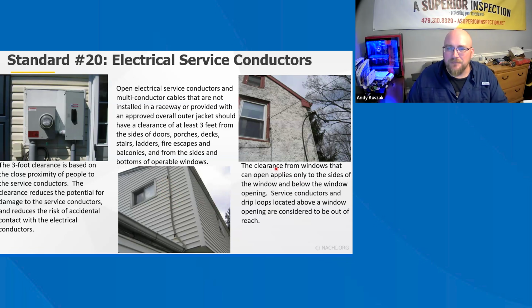Clearance from windows that can open applies only to the sides of the window and below the window opening. Service conductors and drip loops located above a window opening are considered to be out of reach. And I think we're going to go over this in the deck class next week. But a lot of times decks are built after the fact, after the electrical service has been installed. And so sometimes that deck is the only way to install that deck. Well, then part of that contractor quote should include advising the client to have their electrical service moved. Because if that's the only place the deck can go, then something else has to get moved.